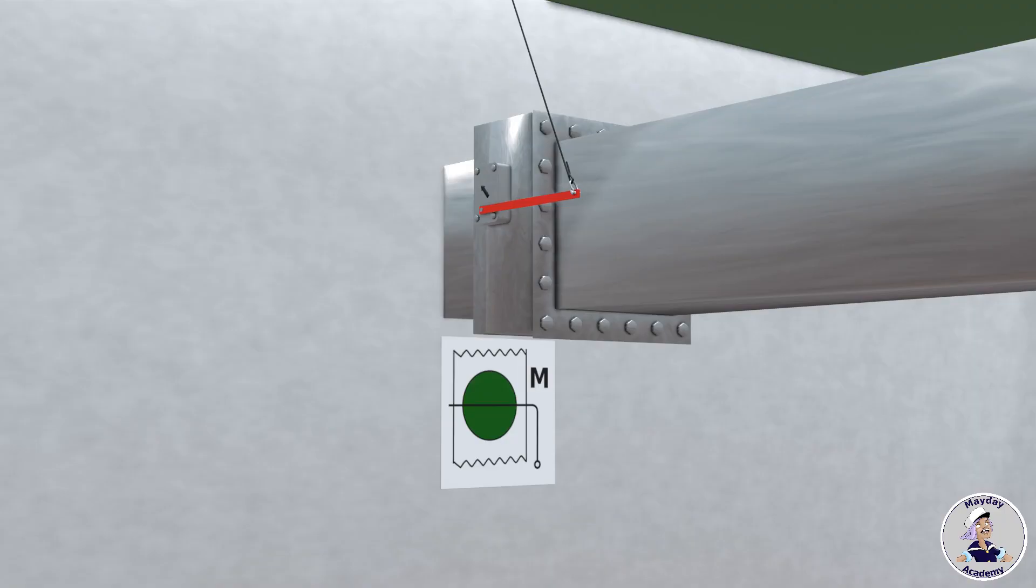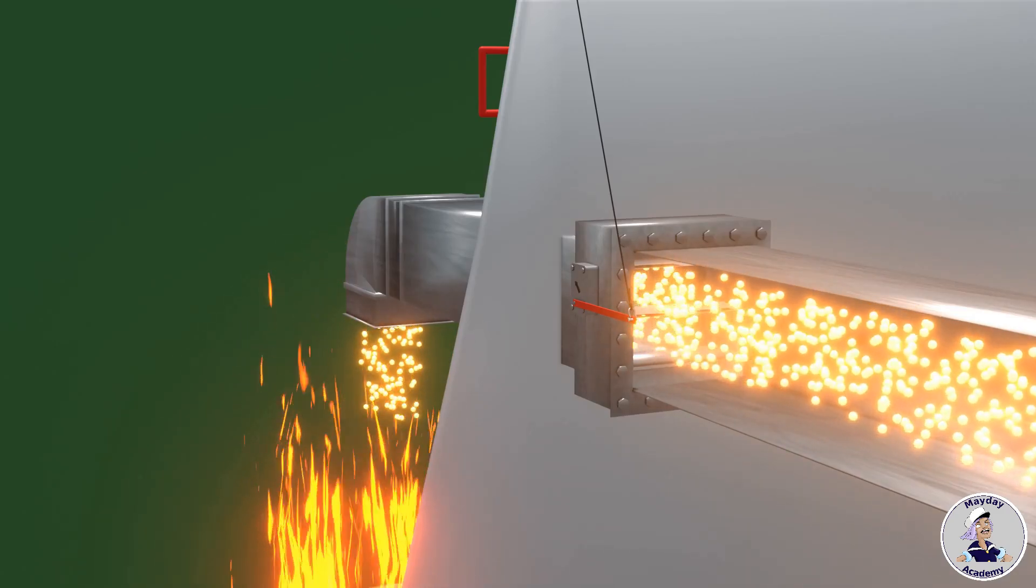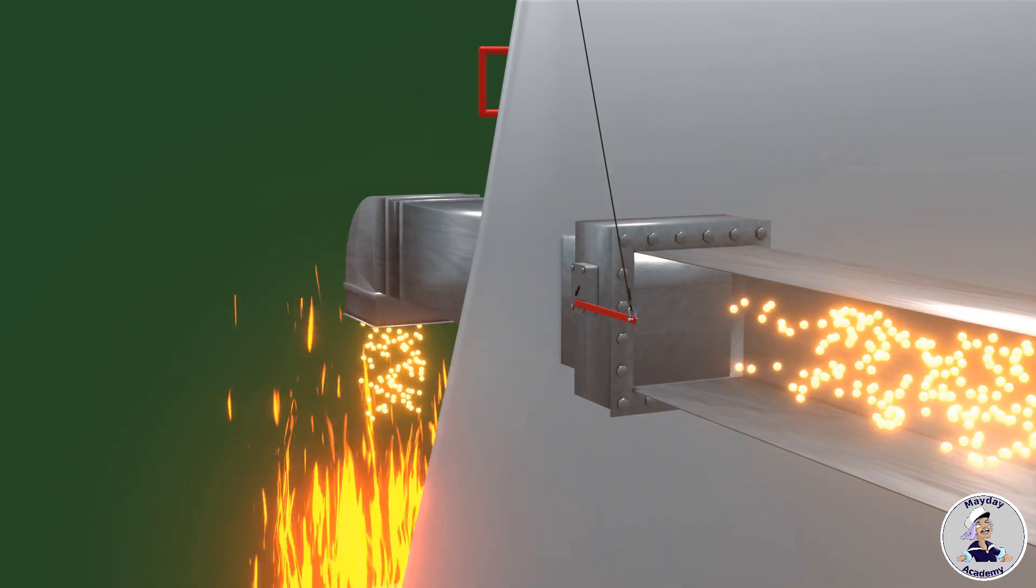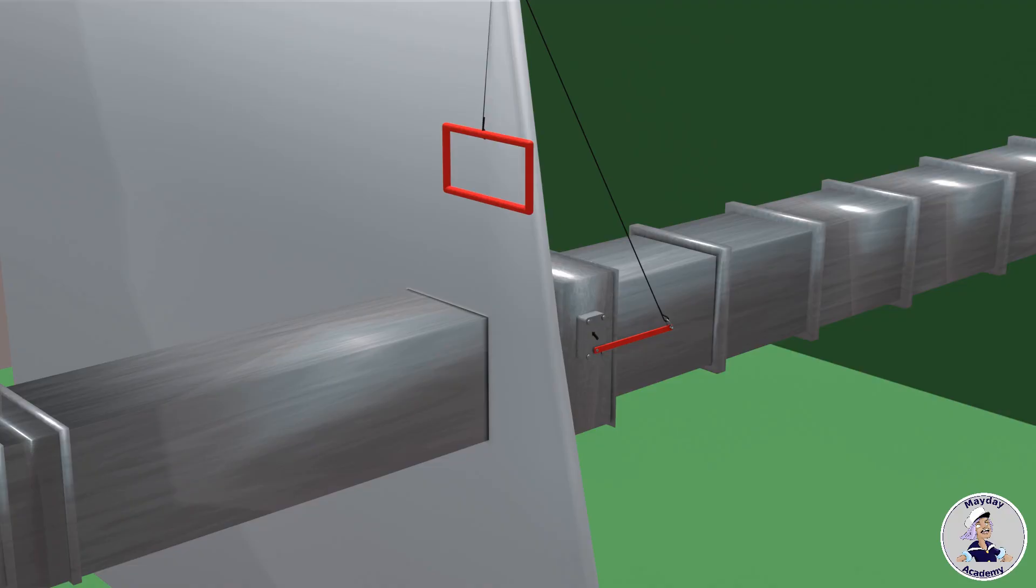Fire dampers, indicated by specific icons, must be installed in all ventilation ducts penetrating Class A compartments. These dampers close automatically when detecting heat, blocking passage between compartments. They can also be operated manually.